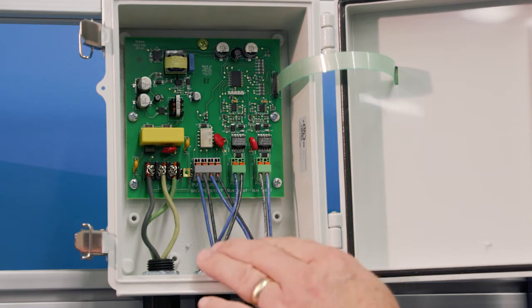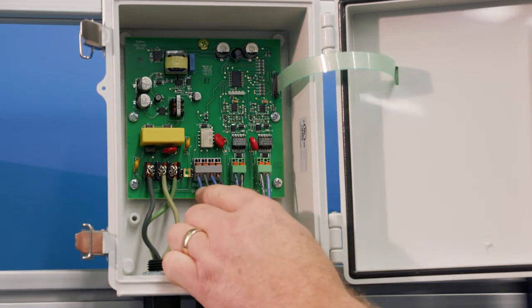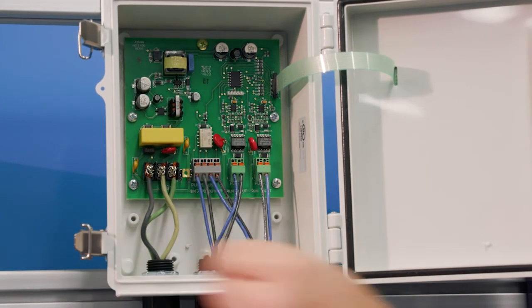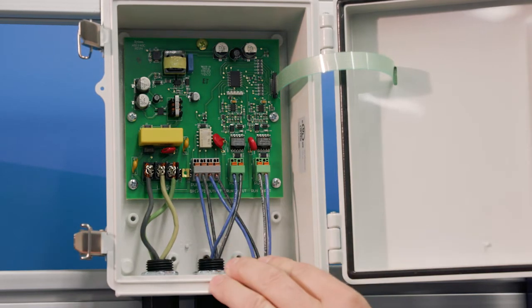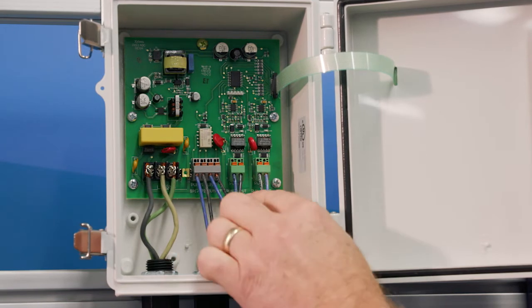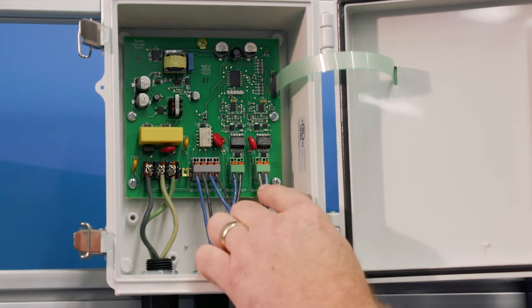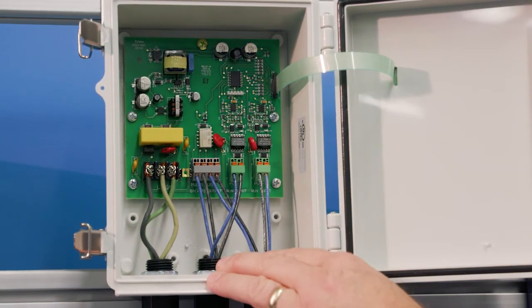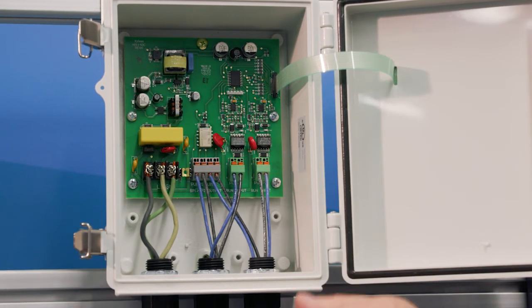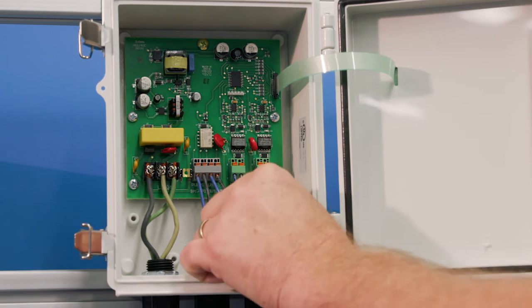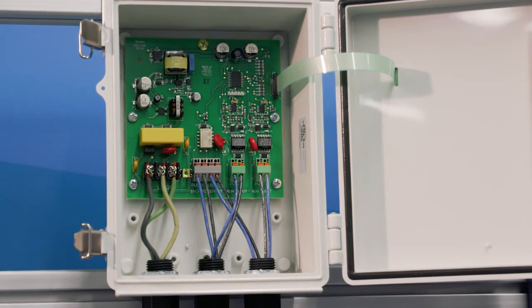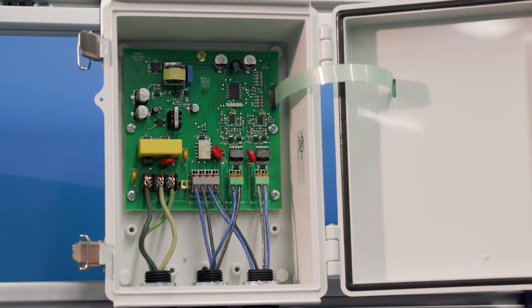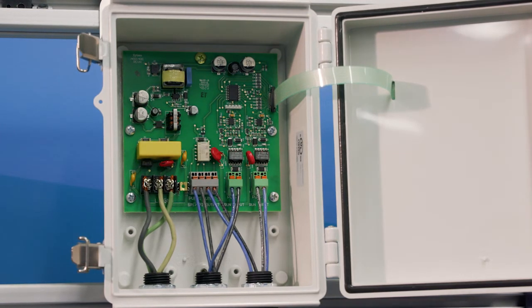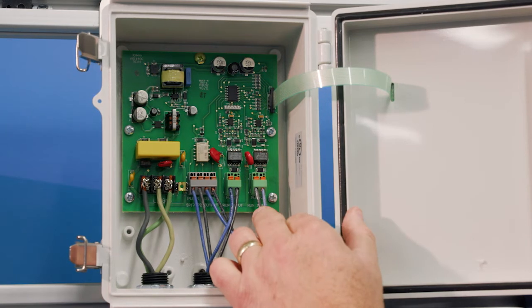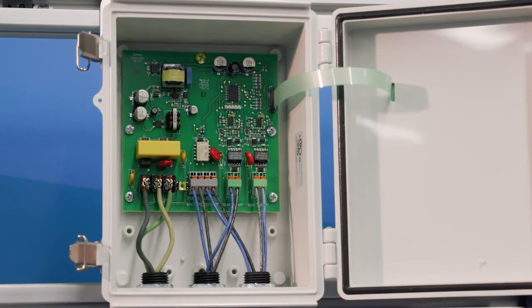And so if we just kind of take a look here at pump 1, this is going to pump 1 here, pump 2 going to pump 2, and we also have some other terminals. Again, it's clearly labeled pump 1 and pump 2. So one thing that's interesting about this is for, again, lead lag alternation based on runtime, we can see that we have wires to the relay. So if we look at the relay here, we can see that we're wired to the relay. So if we just follow these here, that's your input terminal here. So input to the relay, and again, your other unit is going to be exactly the same.